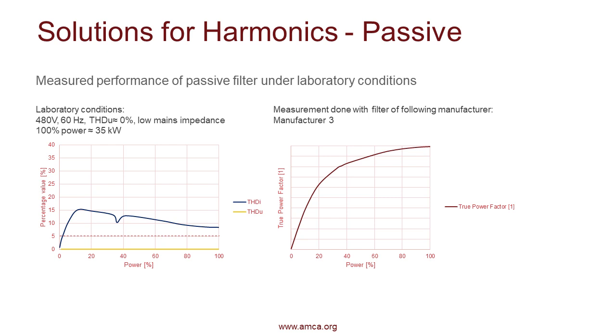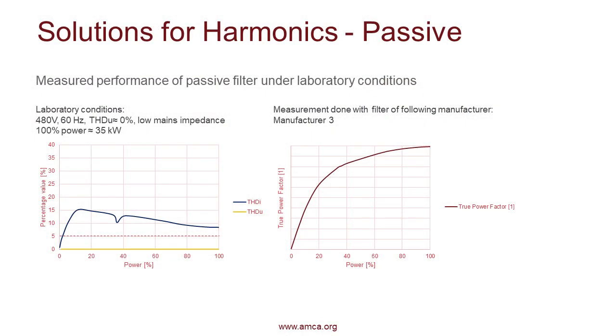different results. And then we can look at a third manufacturer, and so we can see the power factors are fairly similar. It's 1 at 100% or close to that 1, and it starts dipping. But then on the left side, we see an interesting dip at around 38% power. And then as it goes to less than 20%, it's increasing above that 15%. So really looking at your total site, your unit, how your equipment is working with that passive filter is important. Each passive filter is kind of leading to a different result.